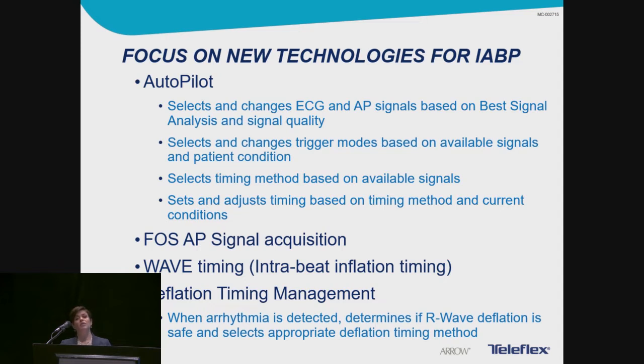And within the Arrow systems, we do offer 6 timing methods. There are 3 inflation and 3 deflation methods. Wave and R-wave inflation and deflation provide real-time intrabeat timing, and they are going to be selected when appropriate. Autopilot, last but not least, will adjust and update timing settings based on the timing method selected.